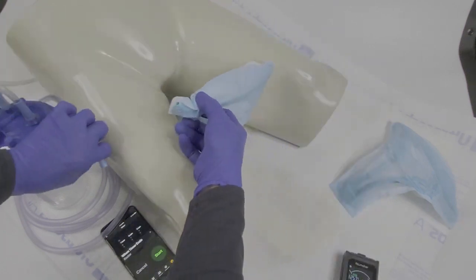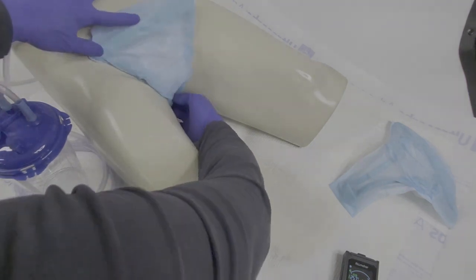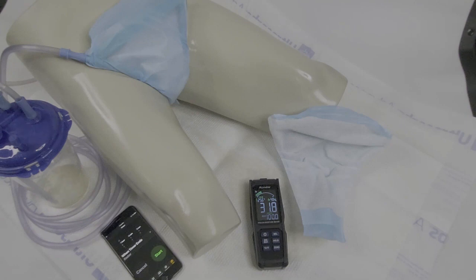The wet UNISUC liner is placed back onto the mannequin as the suction hose is attached, comfortably secured onto the mannequin ensuring minimal leakage. The suction device is initiated. Approximately 100 milliliters of urine is suctioned from the UNISUC device. At this time, UNISUC is saturated in urine, but a significant amount of urine was immediately pulled away.